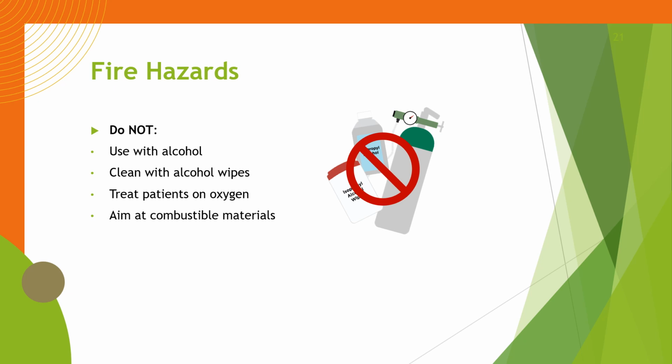Fire hazards, so anything with tanks, alcohol wipes. Make sure that you are not disinfecting the laser with any alcohol, because it can catch fire and it will start real quick if the laser is on and the tip gets pressed by accident, like if you press on the pedal. Usually the pedal has a safety block, so it won't press on its own, but just be really careful. When you're done using the laser, right away go ahead and turn it off and be done with it.